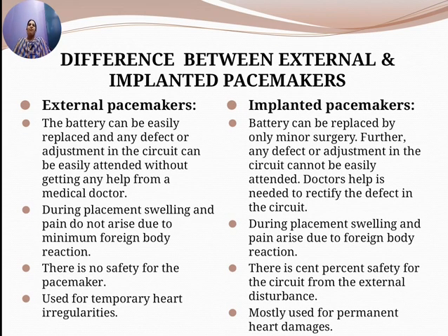So the other differences between external and implanted pacemakers are: in the external one, the battery can easily be replaced and any defect or adjustment in the circuit can be easily attended to without getting any help from a physician or a doctor. But in the implanted one, the battery can be replaced only if you do a minor surgery again, and the defect or adjustment cannot be done by anyone other than the doctor. The doctor's help is a must here to rectify the defect in the circuit.